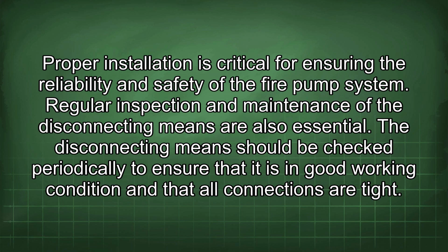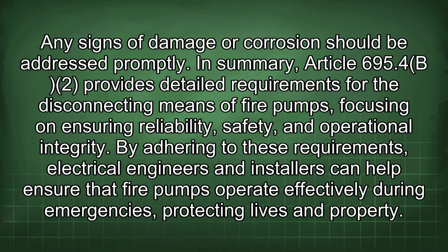Regular inspection and maintenance of the disconnecting means are also essential. The disconnecting means should be checked periodically to ensure that it is in good working condition and that all connections are tight. Any signs of damage or corrosion should be addressed promptly. In summary, Article 695.4 B2 provides detailed requirements for the disconnecting means of fire pumps, focusing on ensuring reliability, safety, and operational integrity. By adhering to these requirements, electrical engineers and installers can help ensure that fire pumps operate effectively during emergencies, protecting lives and property.